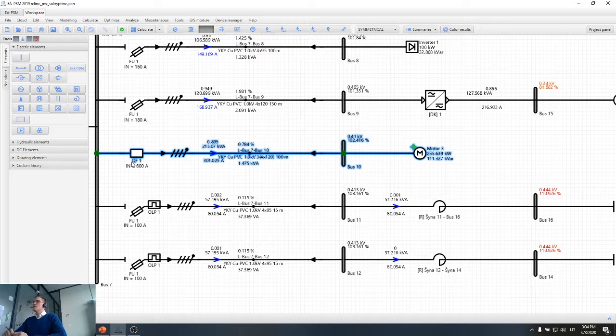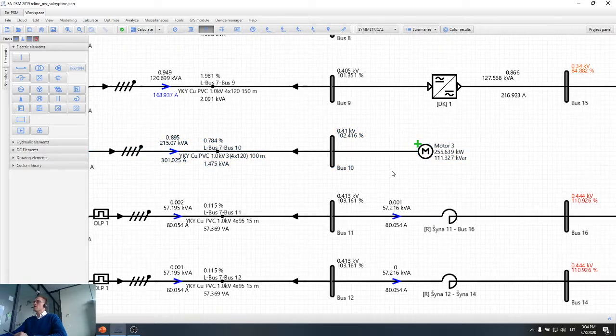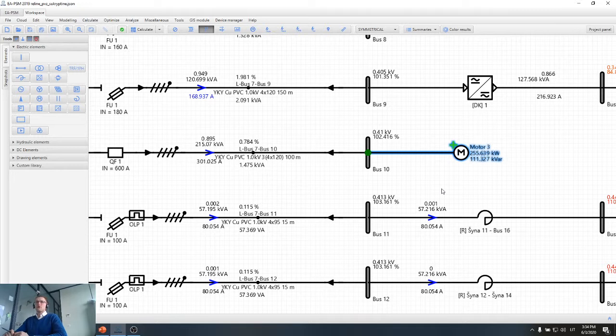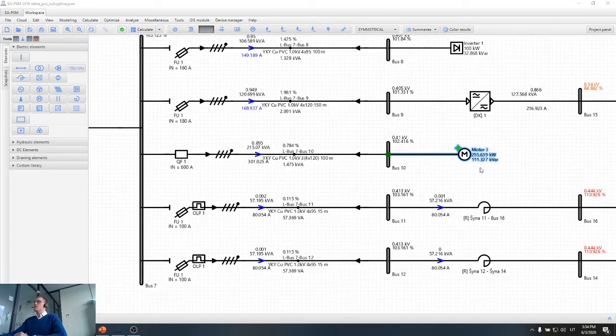And motor basically has much more requirements regarding the protection coordination. First idea regarding the motor is that it is very sensitive to unsymmetrical operation of the network. So for example, if we have unsymmetrical voltage, let's say 5% unsymmetrical voltage, this would cause motor overheating of about 40 to 50%. So only 5% of unsymmetrical operation will cause very huge overheating for the motor. So basically for the motor we need to protect it from the unsymmetrical operation somehow. Also we need to protect the motor from the short circuit.